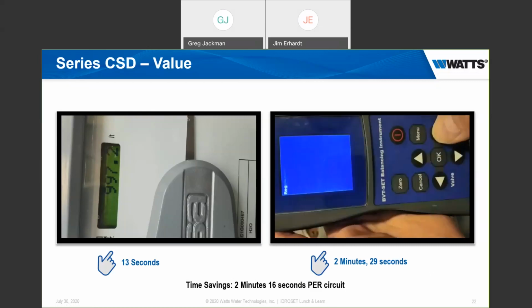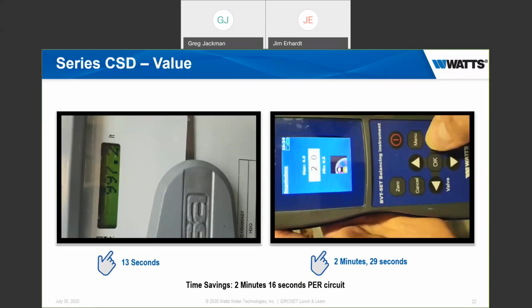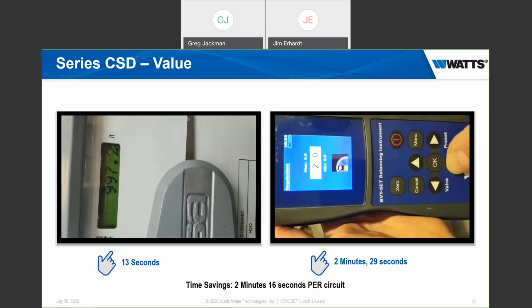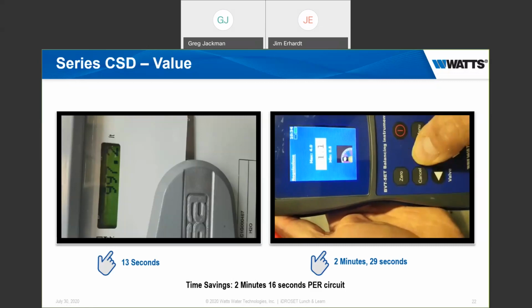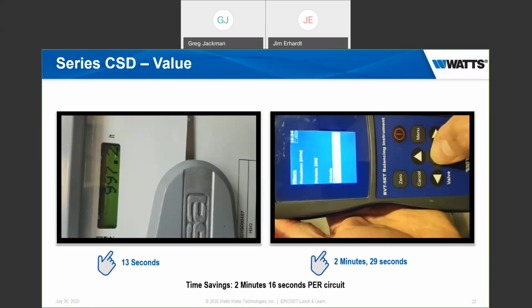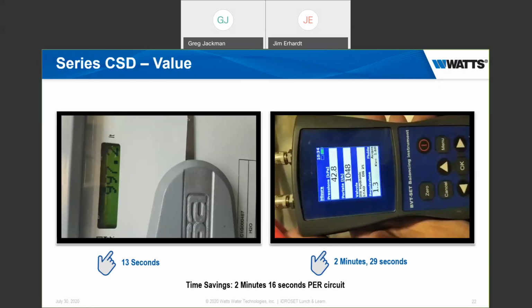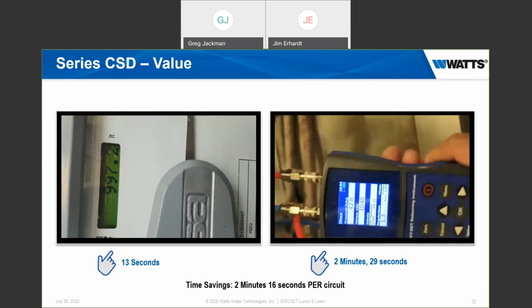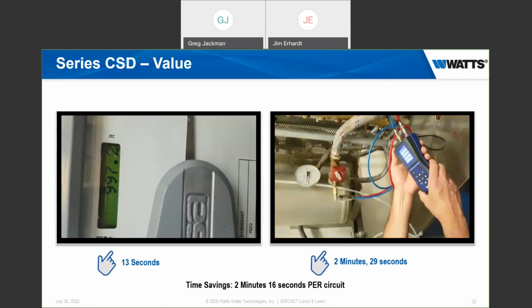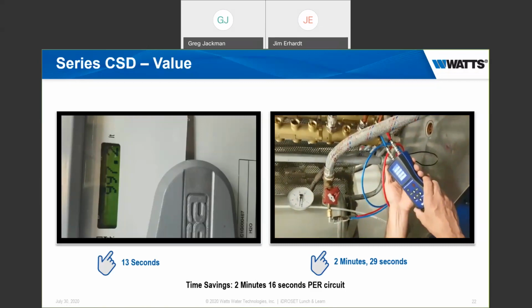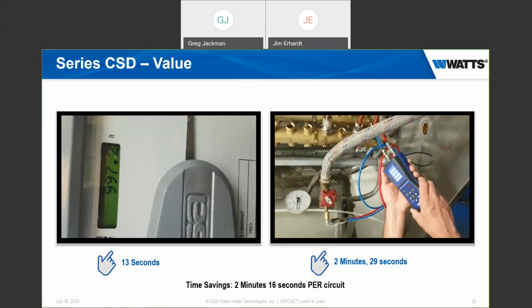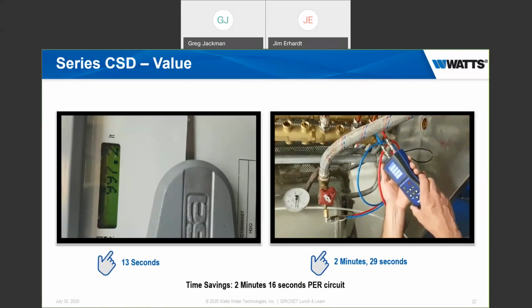Yeah, he might have been able to get it done in 2 minutes, but no mistake about it. Using a standard circuit setter with an external instrument is a very tedious and time-consuming process. This is where the iDROSET is going to save a ton of time on the job. We no longer have to go through this whole process as shown on the right side to estimate what the flow is. We can read the flow directly, turn the hand wheel, set the flow to where it needs to be, move on to the next one.